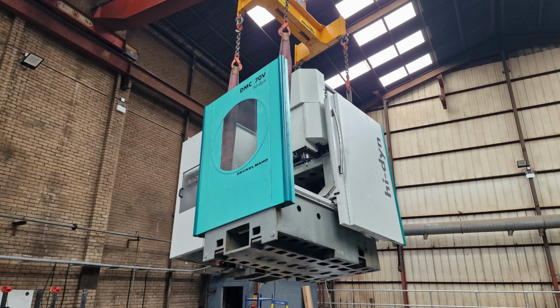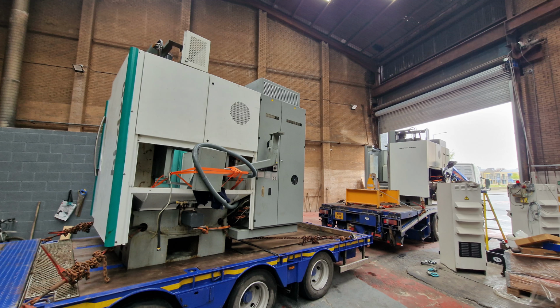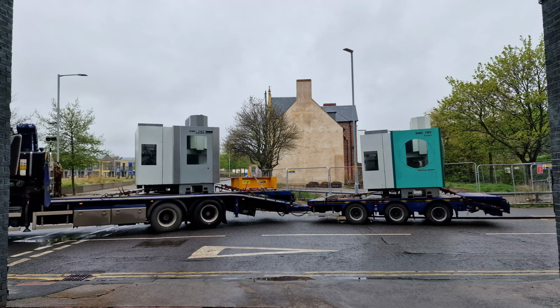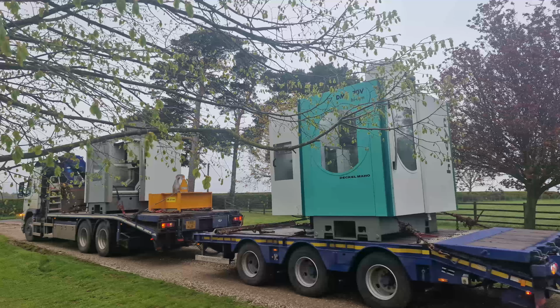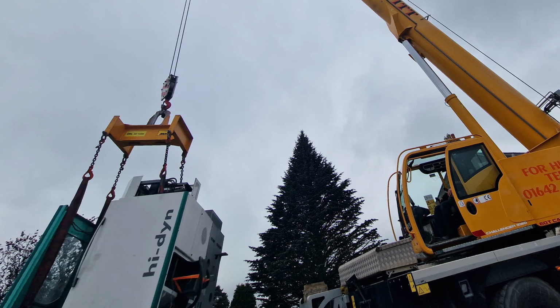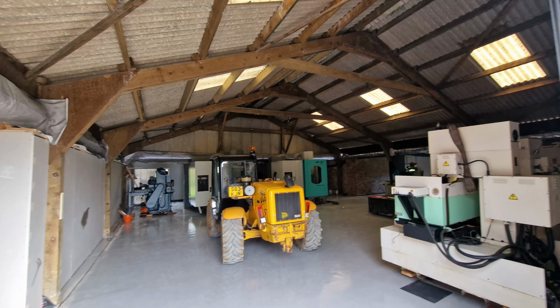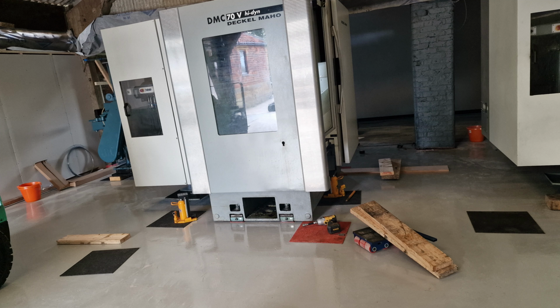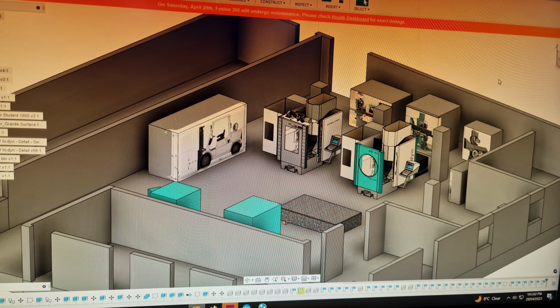We recently moved factory locations, and this location happened to not have three-phase grid power. In order to obtain such a utility, in our case, was going to be in the range of 6 figures. That entails bringing in a new transmission line from the closest substation, a new transformer, and all the groundwork that goes along with such a big task. Not to mention the lead time would have been very long, in the range of 3 to 6 months. That's okay if you can justify that with your business plan, but for what I'm doing right now, that simply isn't economical. So with that being said, let's start at the beginning of the conversion system.